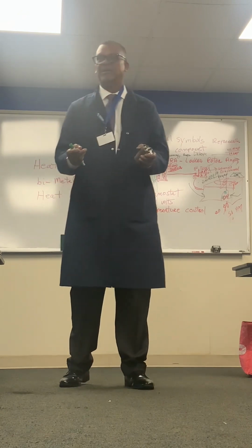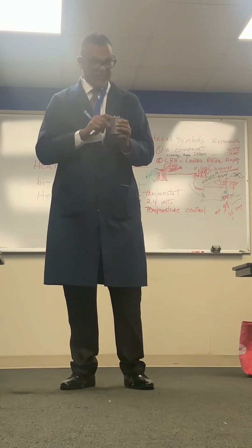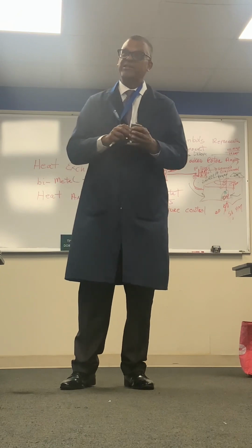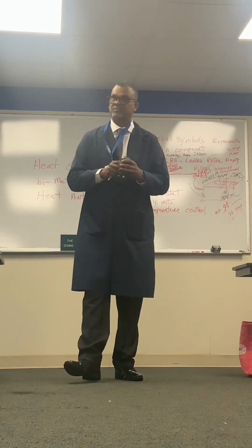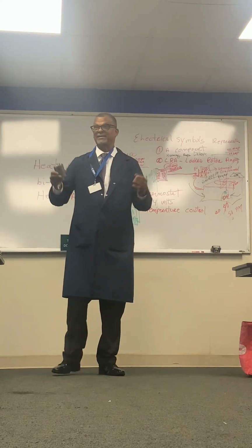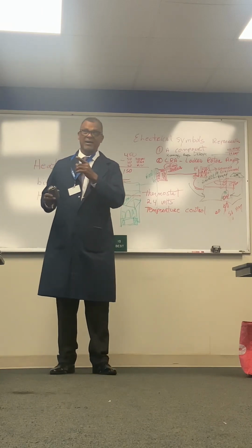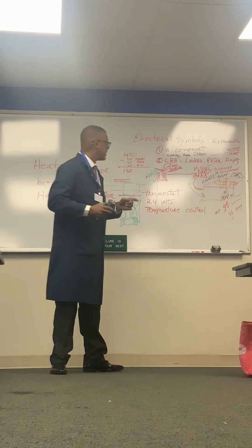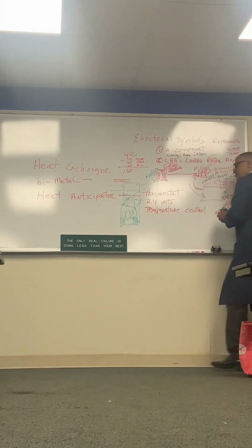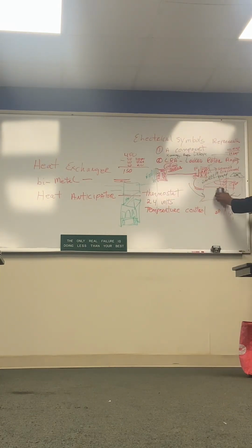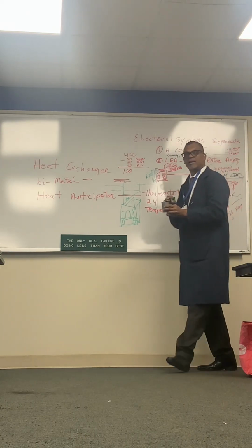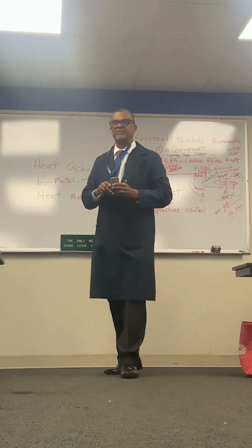They're no good. The other one says fan. What fan are they talking about? Condenser fan? You probably don't know. The condenser fan. Doesn't this make sense though? I could take this component, because that's where it is, and I could take fan and put it on the one from fan. I could take herm from the compressor and put it on here. And I have a terminal left over.